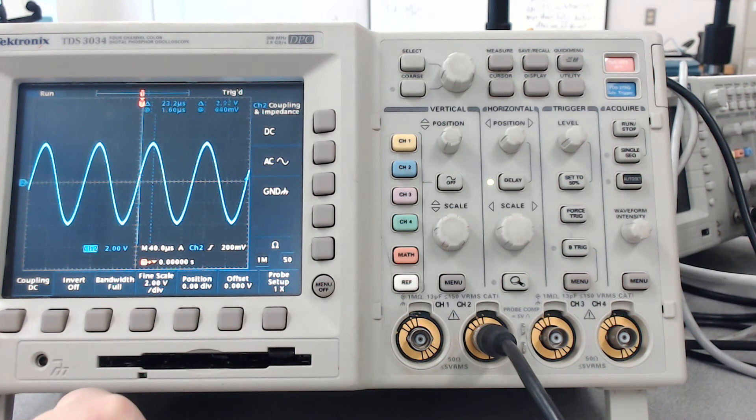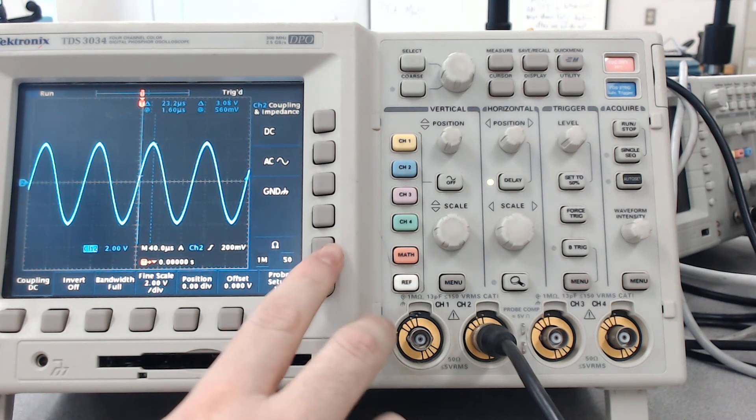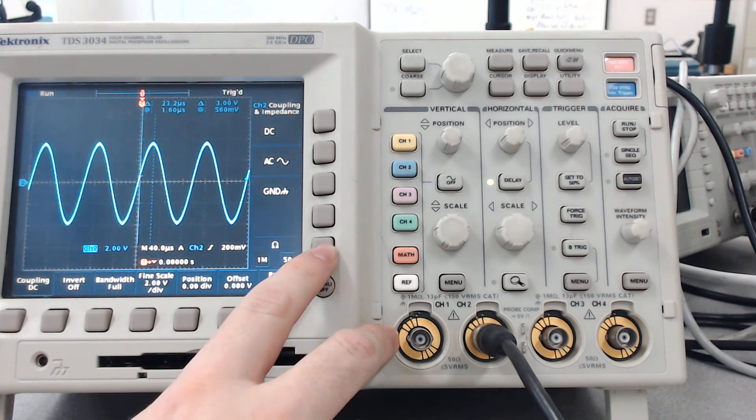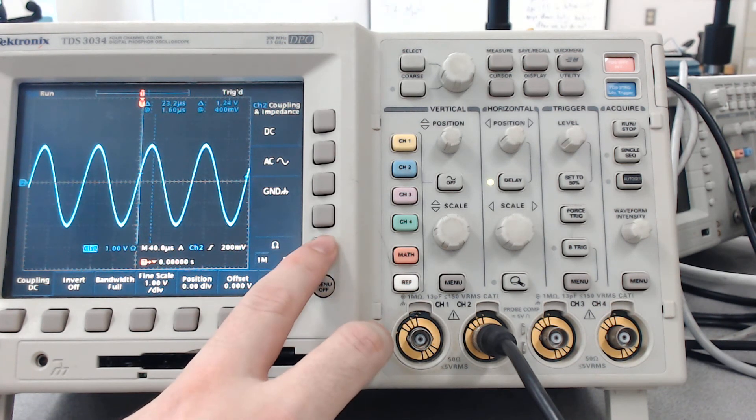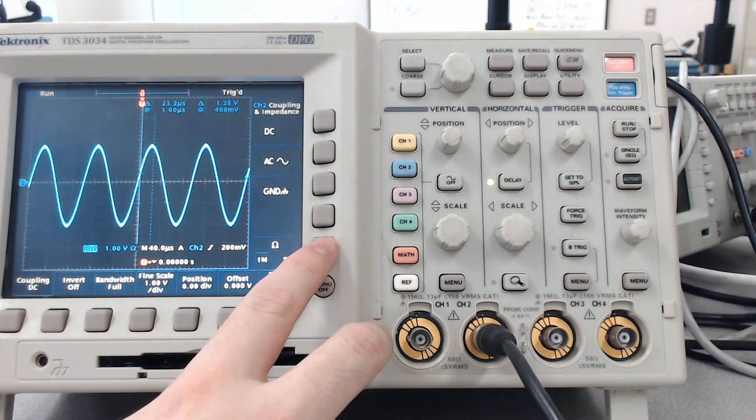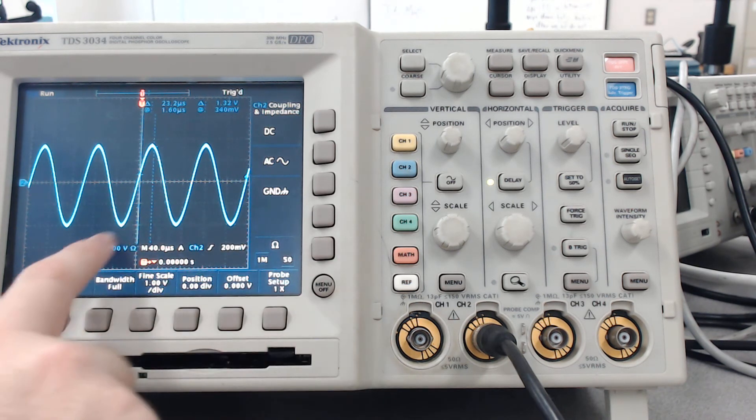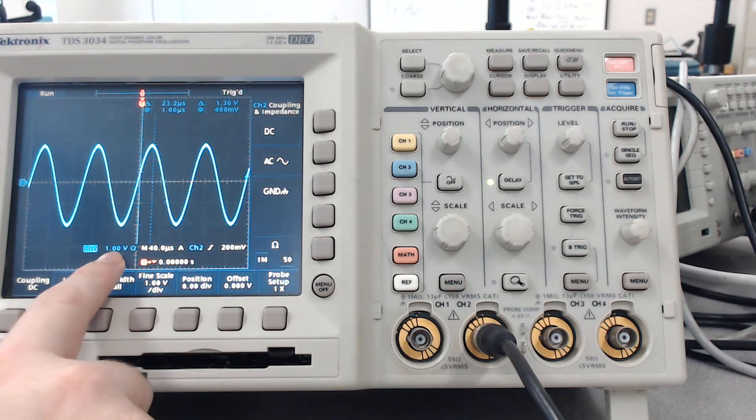So we have a 1 mega ohm resistance. If I hit the button right next to this to switch it to a 50 ohm resistance, it looks like not much has changed, but if you look over here the scale has actually changed.